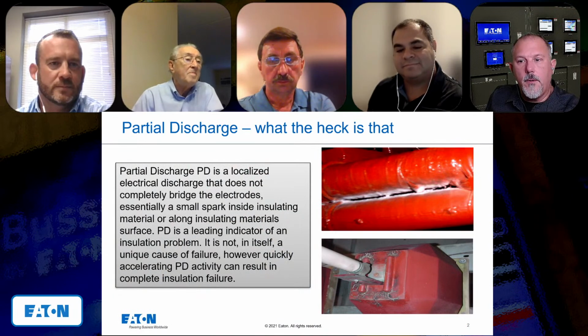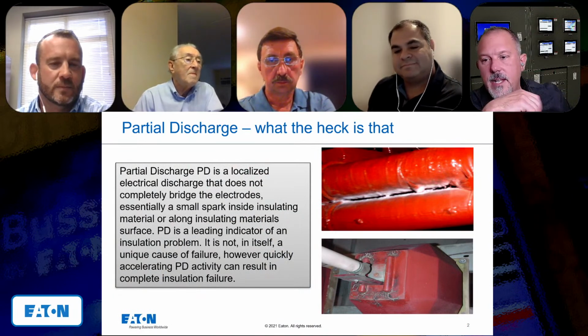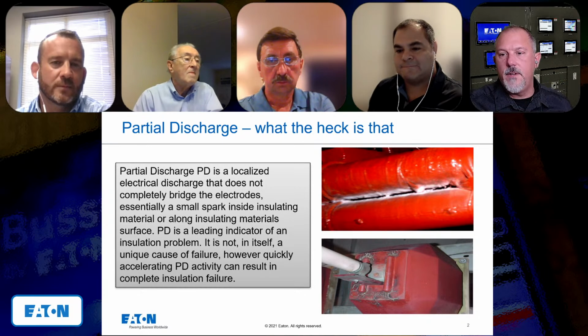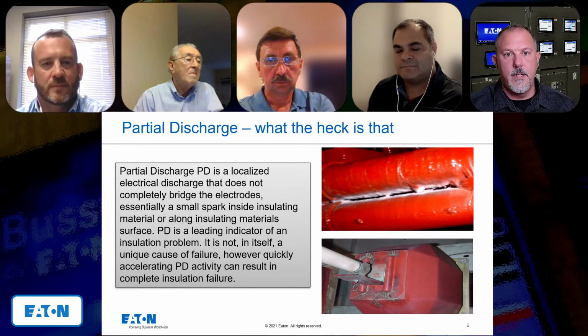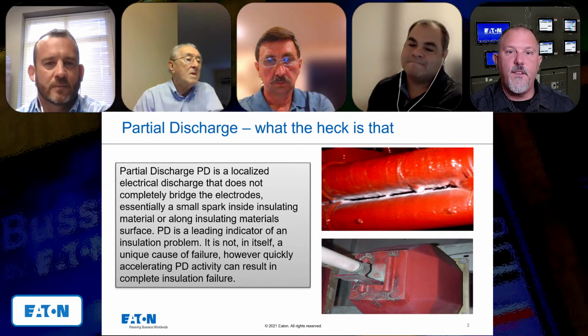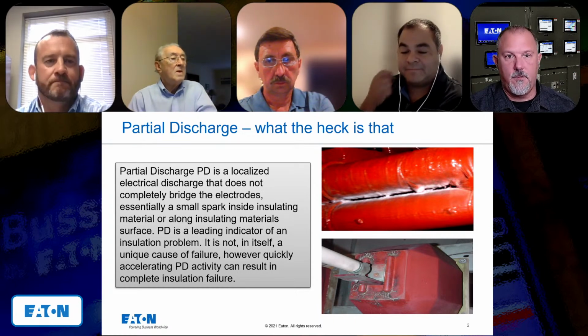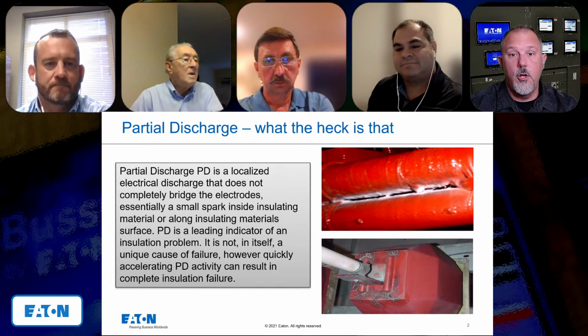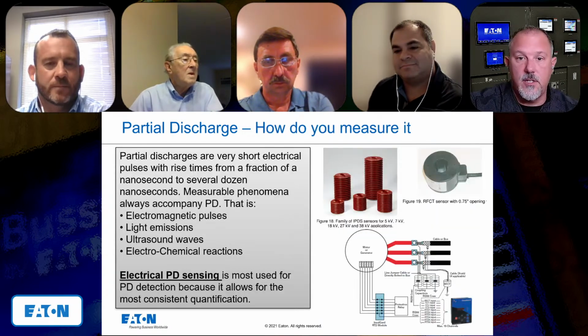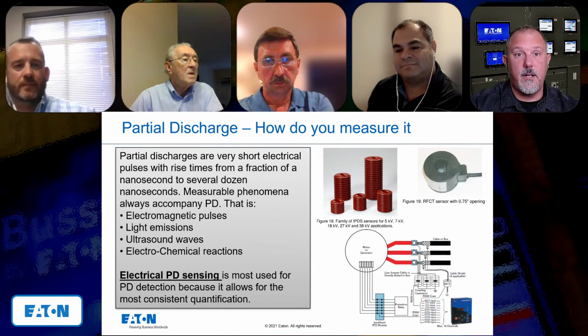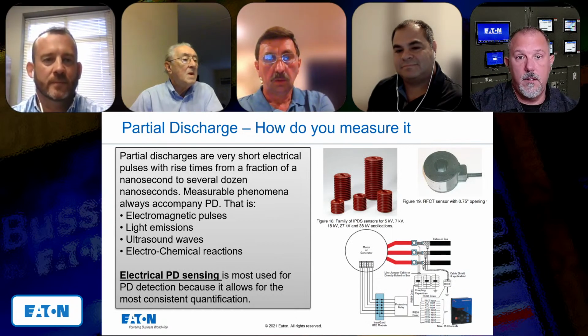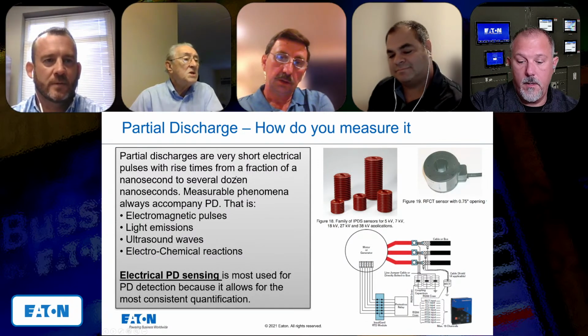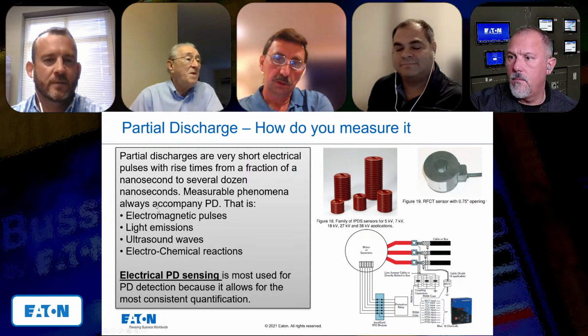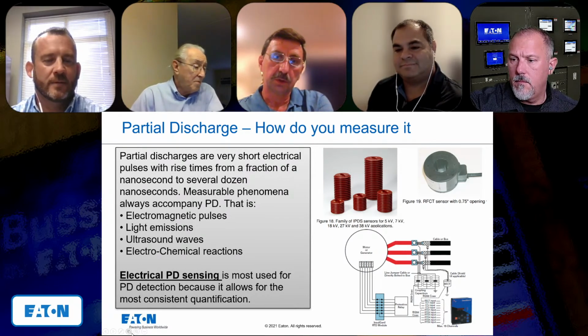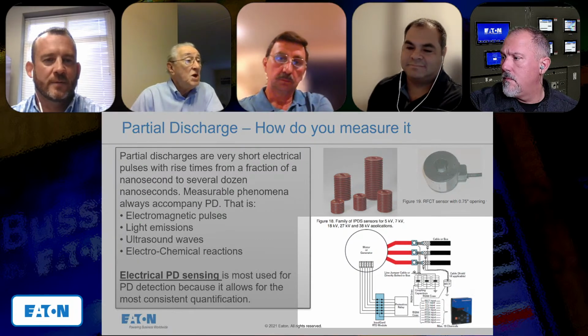Yeah. Okay. And Mohammed is saying, so this isn't something the protective device or relays can detect. We have a relay, right? So there is not a standard like a 50/51 relay, an overcurrent protective device. This is a special device that is designed to detect this. Is that a correct statement? Well, yes. It is not relays. I prefer to say that it's diagnostic equipment.